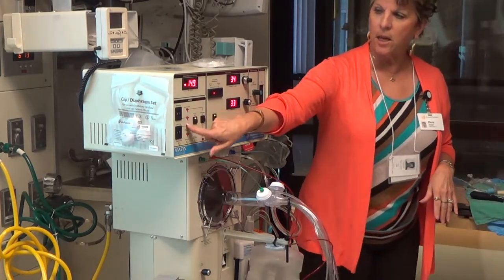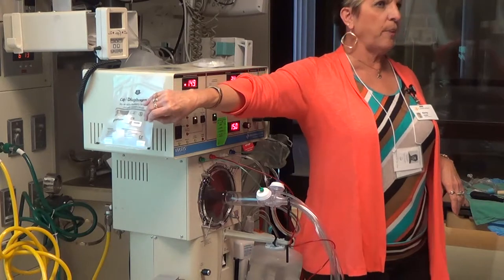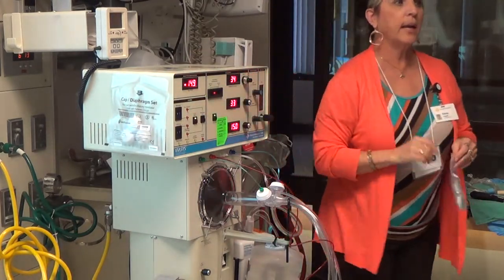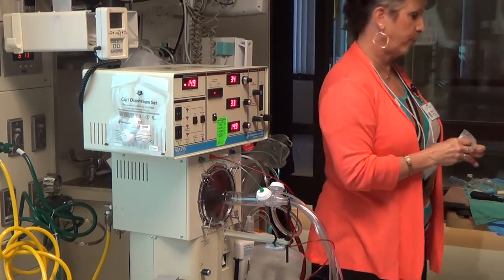Other things that can cause these low pressures are your mushroom valves and your cap diaphragms. I see you guys are way ahead of the game, you keep an emergency pack here. I think they're as important as your bag mask. If one of these goes bad, where do you have to go to get new equipment? Down the hall, out of the room is too far.